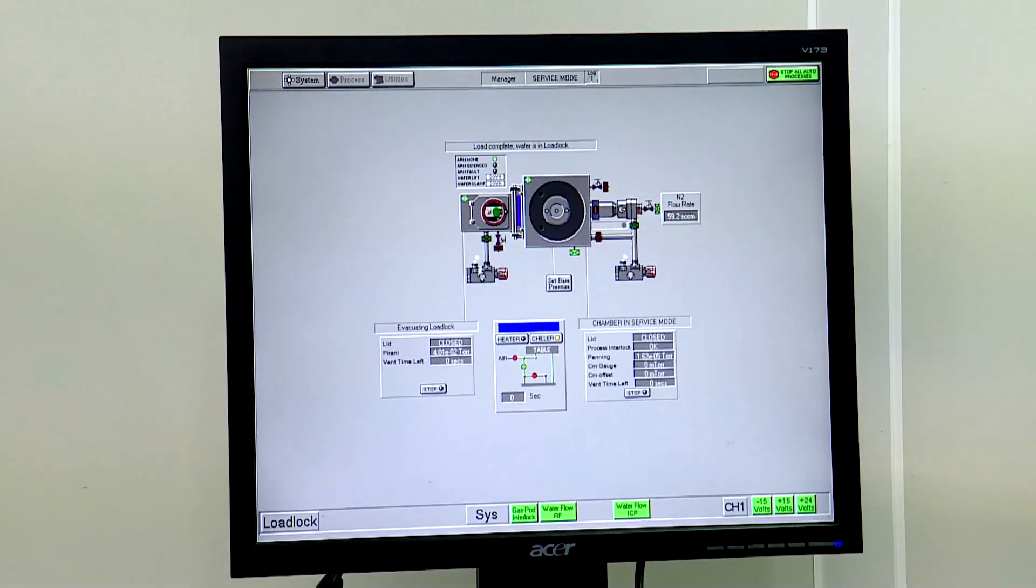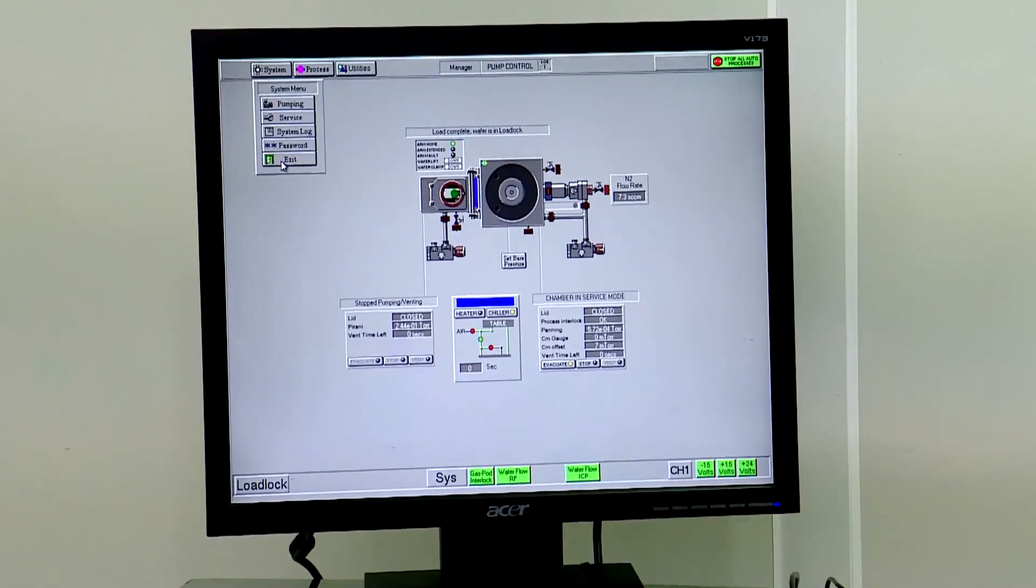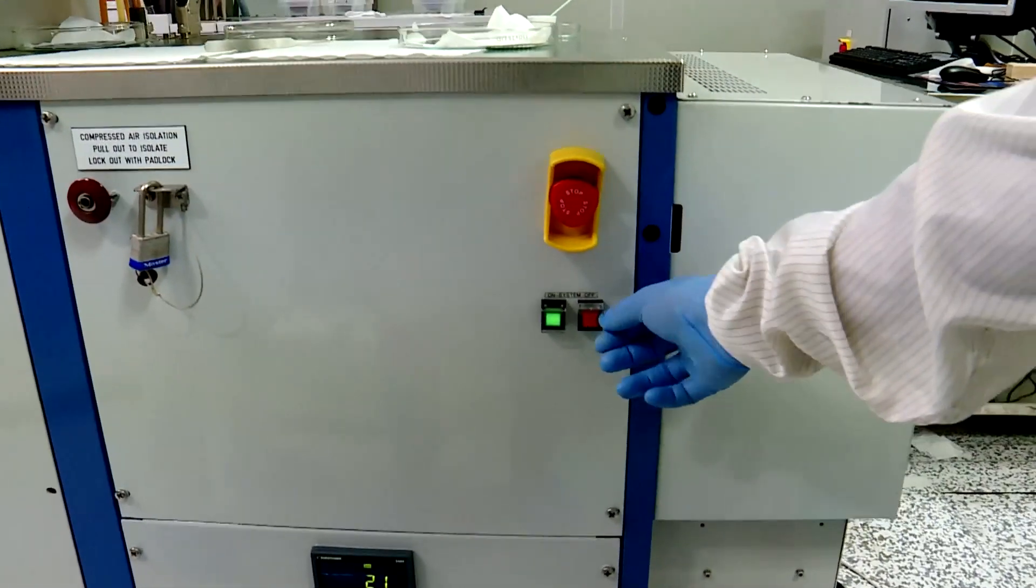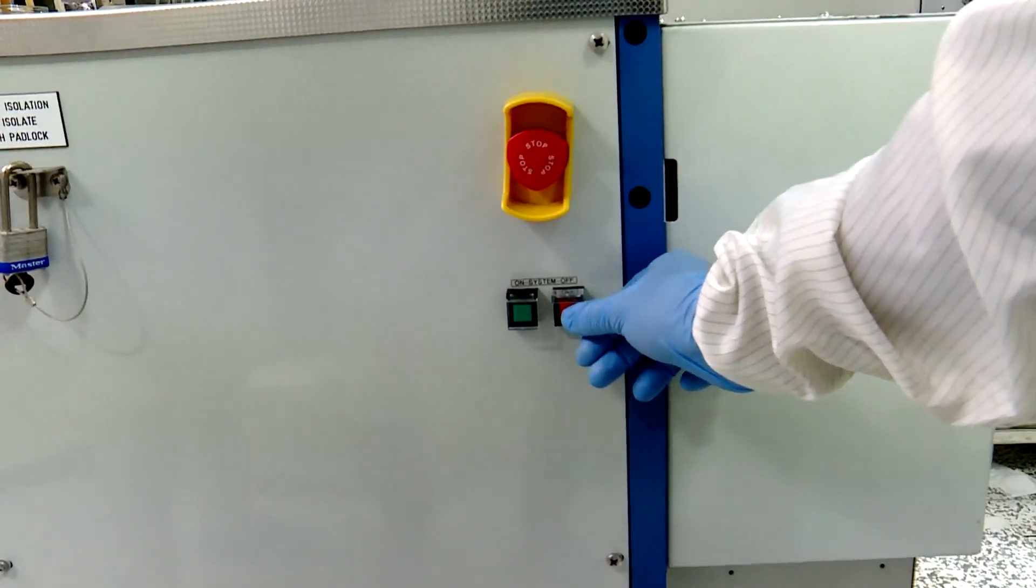Before switching off the system, all the pumps should be turned off. Exit the program and finally close the ICP-RIE.